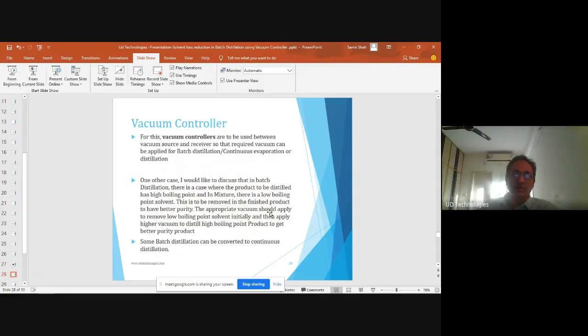So now we will discuss the vacuum controller. The vacuum controller is used between the vacuum source and receiver, so that the required vacuum can be applied to the batch distillation or continuous evaporation. As we have discussed, we have to apply some higher absolute pressure. Because a triple effect ejector is there, there is a full vacuum, meaning around 5 to 10 or 2 to 5 torr. Not every solvent needs this in the reactor. So we have to control the vacuum. How will we control the vacuum?